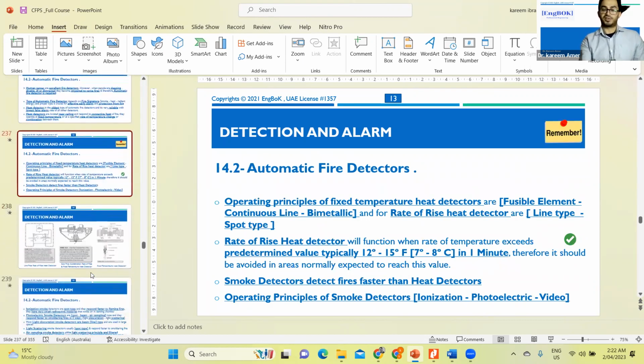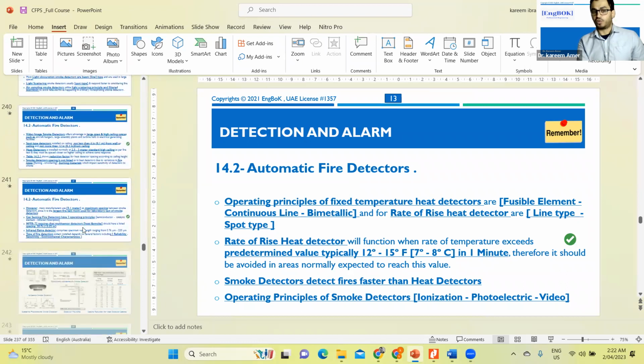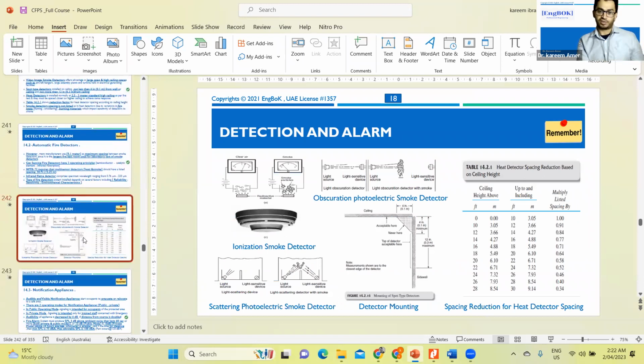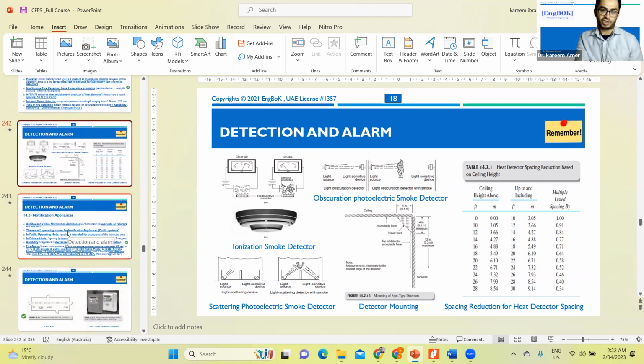What are the types of detectors - heat or smoke? Heat detectors, as mentioned earlier, can be fixed temperature or rate-of-rise. For smoke, we have ionization or photoelectric type. Photoelectric type has two main subtypes: obscuration and scattering. Then we have air sampling and video detection, which are the latest technology.